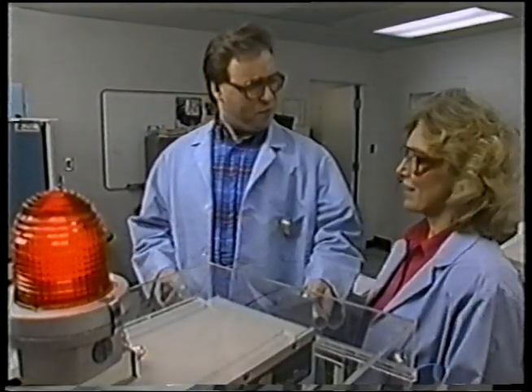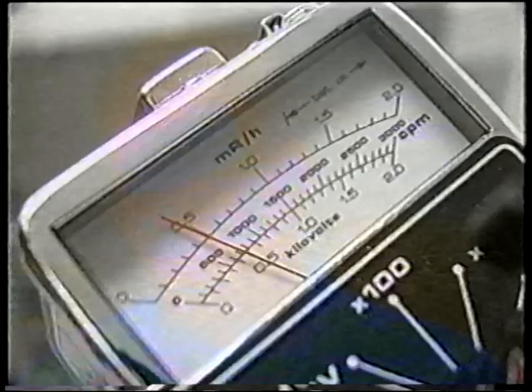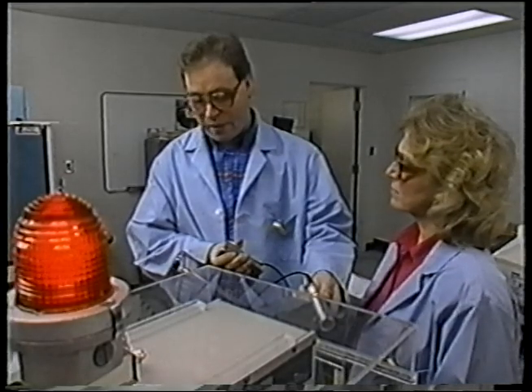Hi, Marty. Ben, you again. What do you mean, you again? Another survey? I'm getting something here. Have you modified this equipment recently? Last week, we expanded the beam to get more signal, changed the collimation. You're getting scatter. Well, it can't be that bad. We can't be getting that much scatter. Sorry, but you are. And Marty, you should have done a survey after you recollimated the beam.